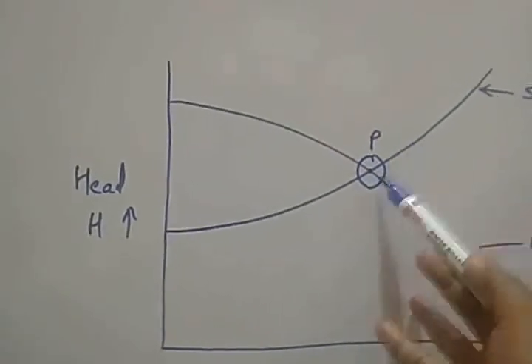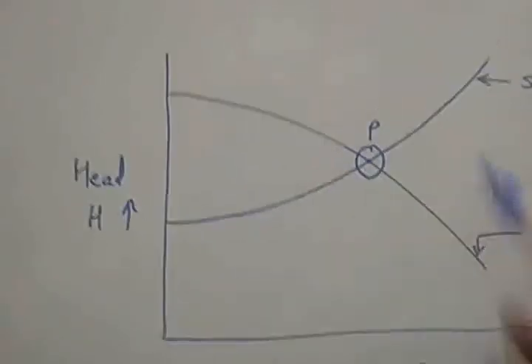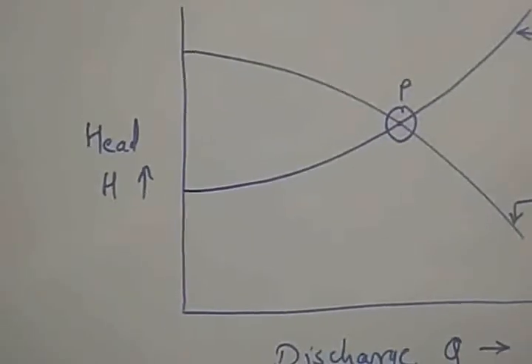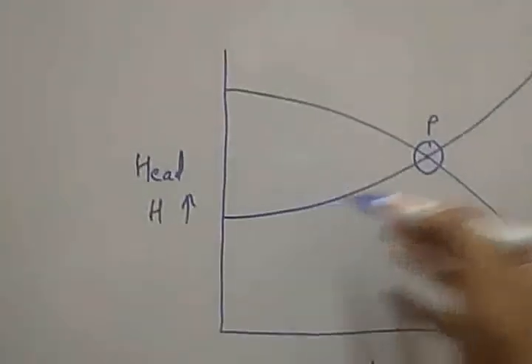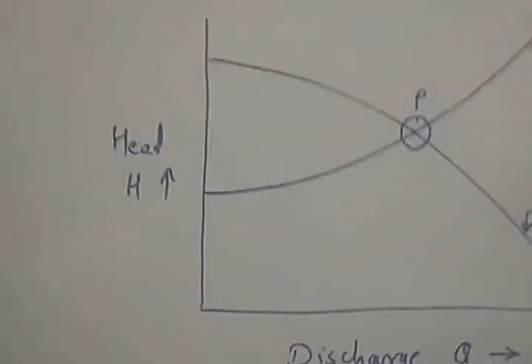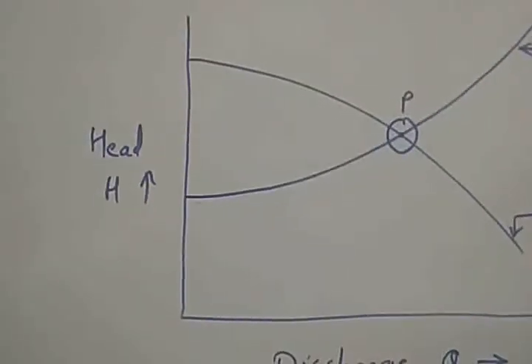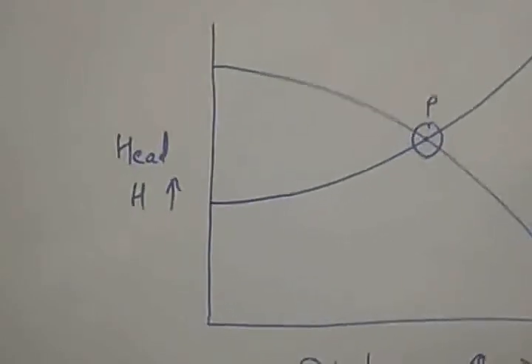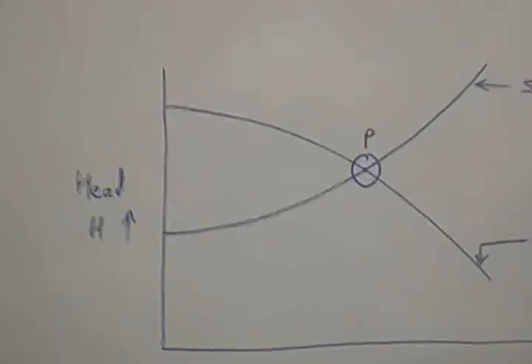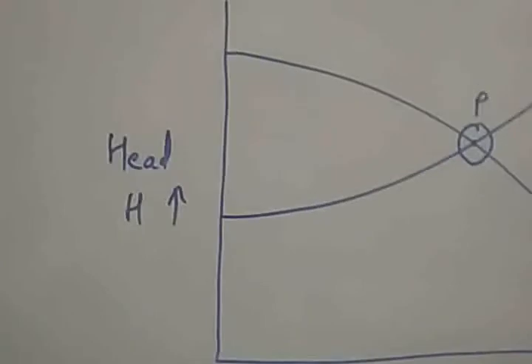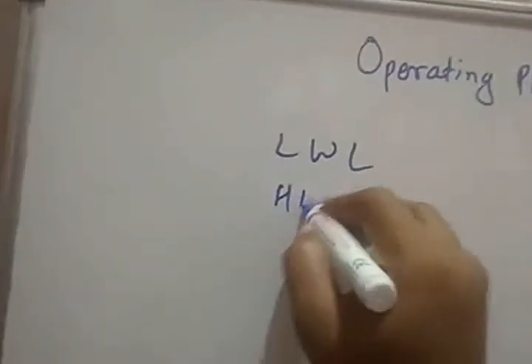Point P gives the head demanded by the system as well as the operating head of the pump for a particular discharge. If the system head curve changes, then the point P will be shifted. This significant change occurs because of the change in the level of the sump, and there are different system head curves corresponding to lower water level and higher water level.